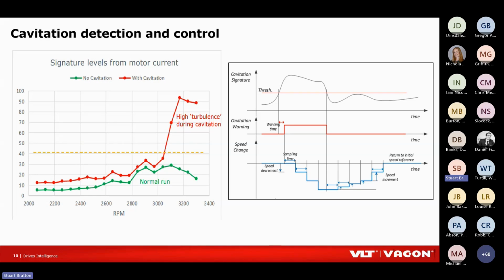normal currents. What we see with cavitation from a pump, we get our little air bubbles building up and exploding and damaging our impeller, is that disturbance to the impeller shows up not only audibly, I'm sure a lot of us on the call have heard cavitation from a pump, but it also shows up in the current that's going out to the motor. So the drive, without needing any additional sensors externally, it's purely using the current sensors that are already in the drive as standard. It can detect this change in current signature, and because of the very characteristic nature of cavitation on the current signature, it's able to identify that that's cavitation and indicate that to the user.